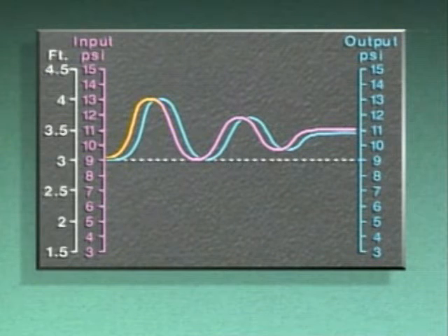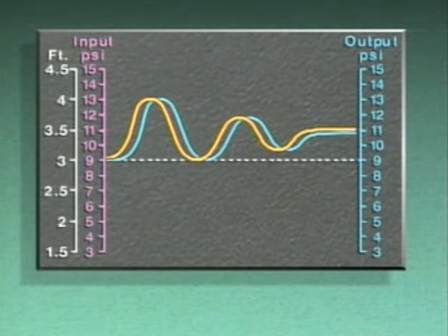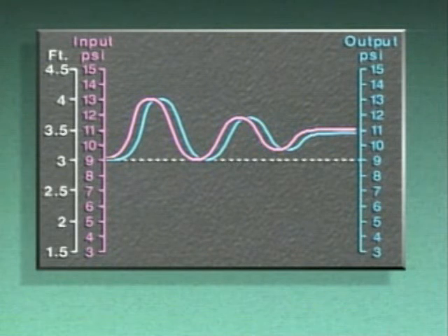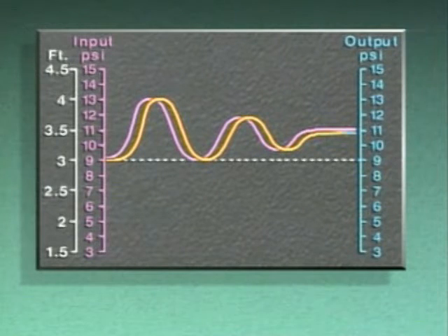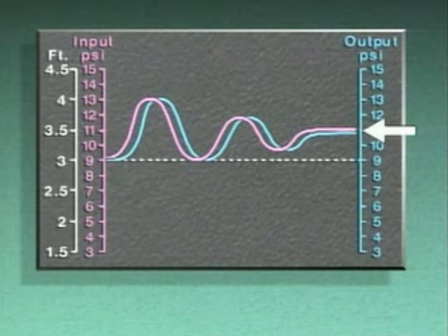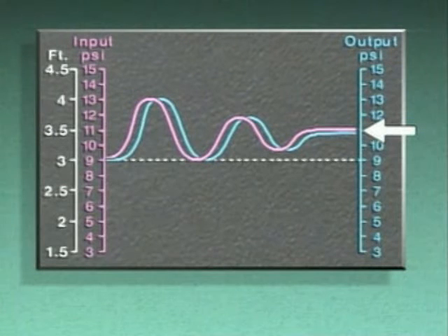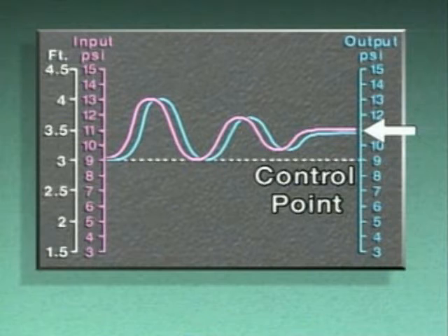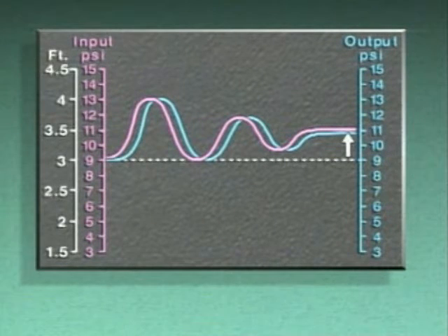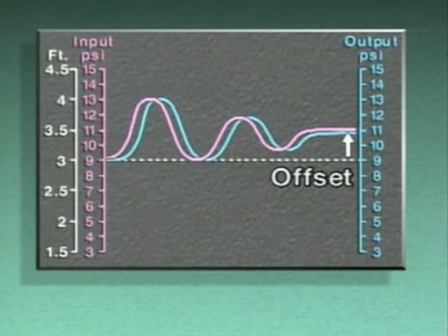That's because the input signal to the controller increased, then stayed high because of the continual disturbance. As a result, the proportional output signal stayed high as well. The higher steady state value that resulted, that is, the higher level that's represented by the input signal, is called the control point. The difference between the variable's control point and its original set point is called offset.